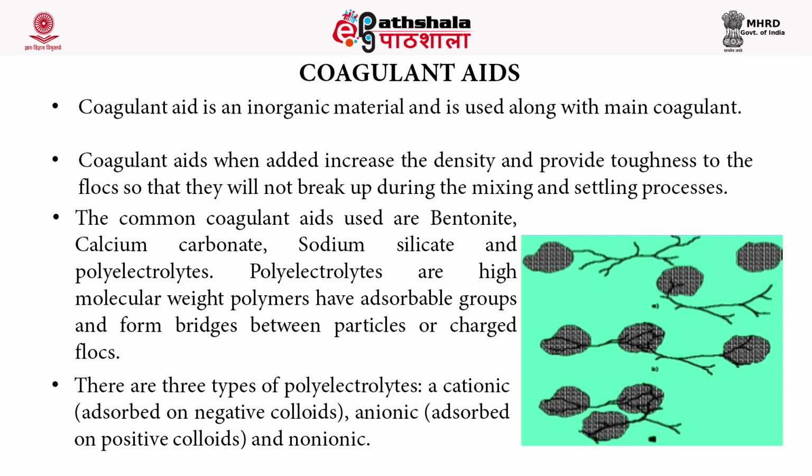Chemical coagulation has been in practice for several decades to precipitate the soluble heavy metals which are present in the wastewater as hydroxides, so facilitating their removal by physical separation through sedimentation. Chemically, the coagulants are either the metallic salts of ferric ions or alum, or they could be polymers. The process of coagulation consists of the following steps.